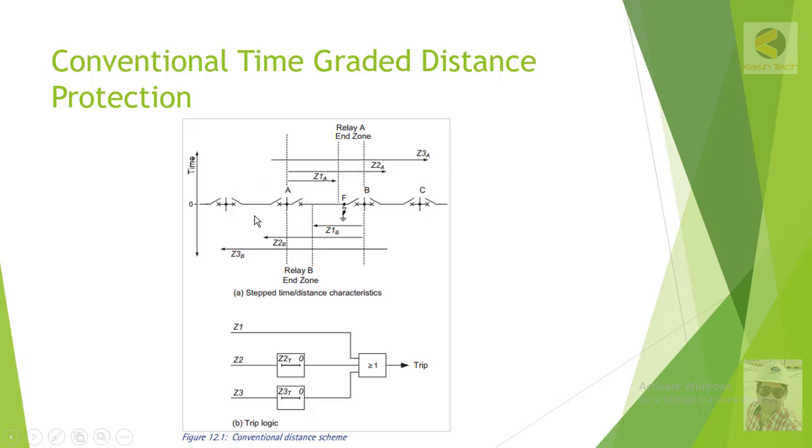This blocking scheme is more in favor of tripping. If the communication is available or not available, in both cases it will trip the breaker at station A. If you want to set the priority to tripping, even in case of communication failure, we can choose the blocking scheme.